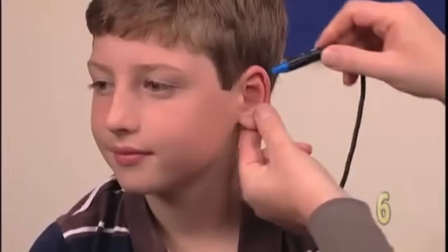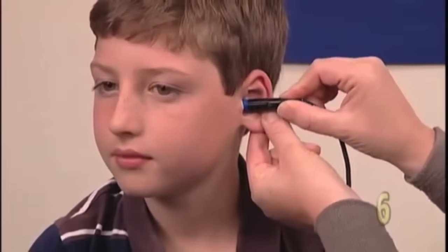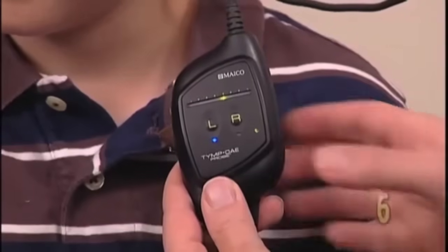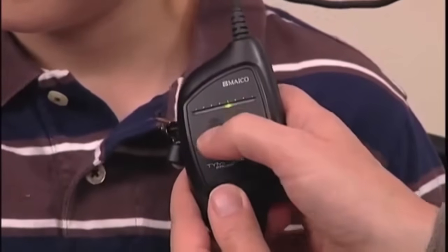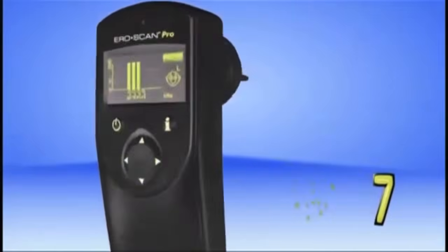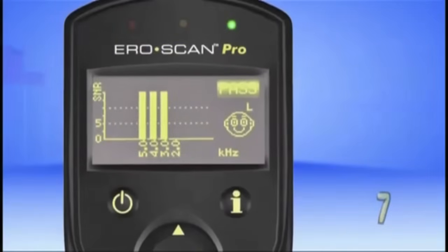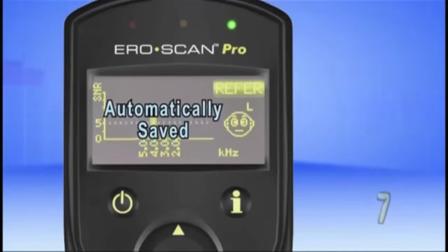Insert the probe into the patient's ear canal far enough to ensure a tight seal. Then, start the test by pressing the button for the appropriate ear on the probe housing or the Ero Scan Pro itself. Once the test is complete, the results can be viewed on the Ero Scan Pro's display screen. The display will indicate either a pass or refer, and display the frequencies tested. A pass indicates the subject passed the screening test. A refer means that the subject should be retested or referred for further testing. This test is automatically saved in memory.